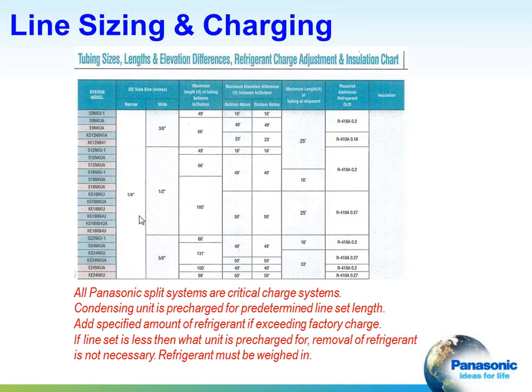I mentioned long line set runs that this equipment is capable of achieving. This is just a sample of the table. There are some systems that can go as far as 164 feet with fairly large changes in elevation. Refer to the table or call us and we can help you out on that as well. The condensing unit is pre-charged for a predetermined line set length. That does vary. Some of them are 15 feet, some of them go up to about 25 feet. You need to look at each system to determine exactly what you need.